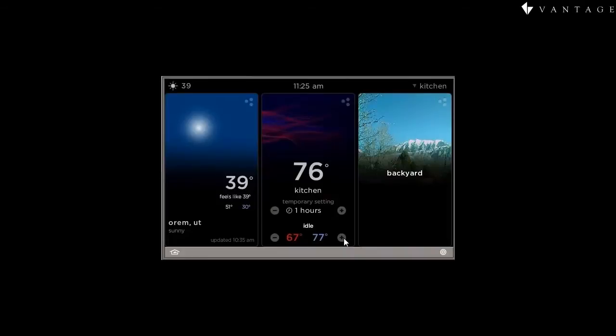Once we have done that, then we see that that appears with an adjustment, plus and minus, and we can adjust that temporary override for up to 6 hours in 1 hour increments. Now, once the override period is over, the regular schedule will resume. As the override period progresses, the display will count down, still in 1 hour increments, to show how much time is left.